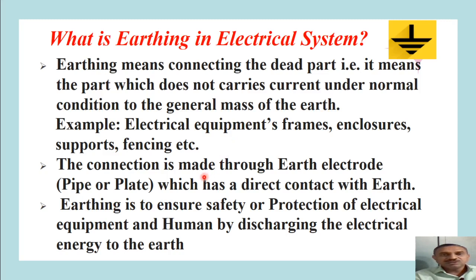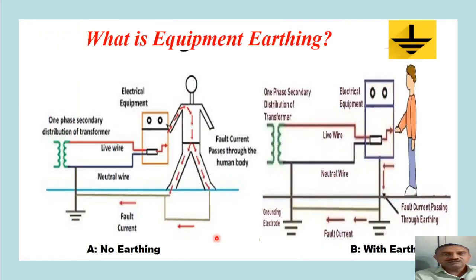Now the connection to the earth is to be made through an earth electrode. The earth electrode can be of two types, either pipe type or plate type. This earth electrode will have a direct contact with earth. So establishing the direct contact with earth will make the potential of that particular part of the equipment or apparatus at the earth potential, that is zero potential. It means that earthing is going to ensure the safety and protection of electrical equipment as well as the human being by discharging the electrical energy which has been accumulated on the equipment frames, enclosure, support or fencing to the earth. Now how this can take place, we'll study here.